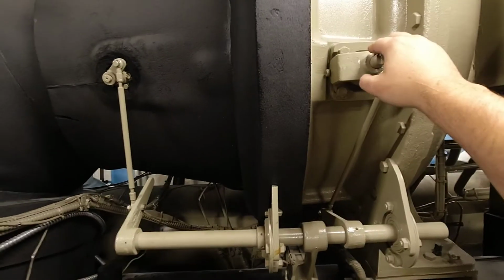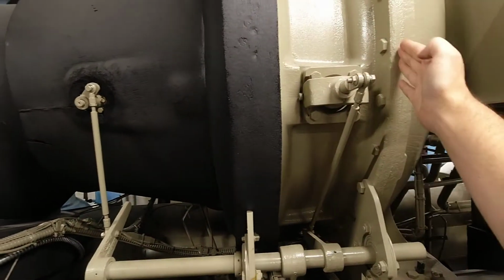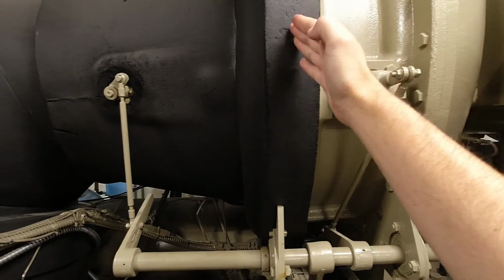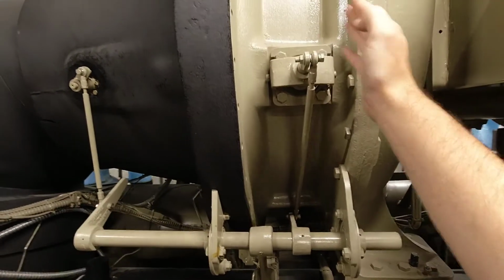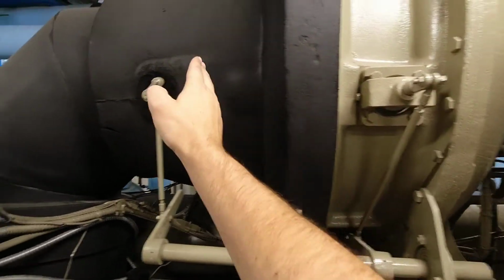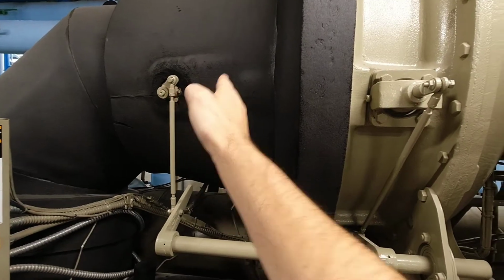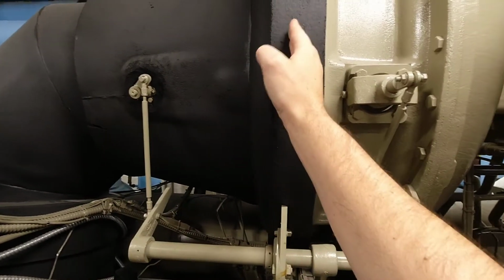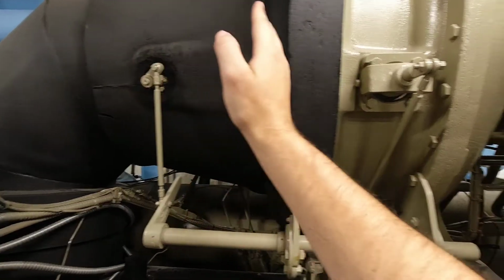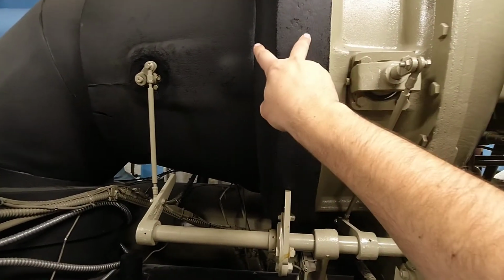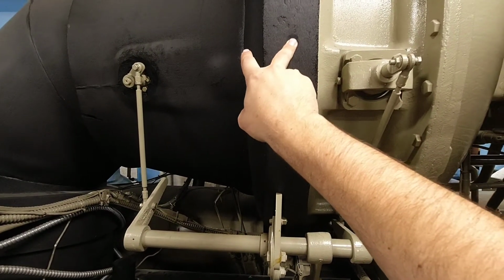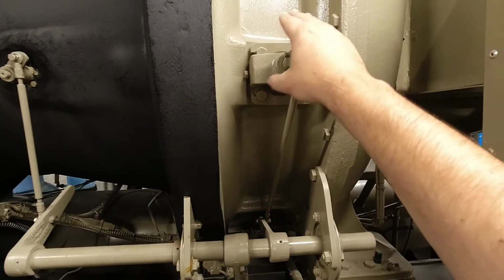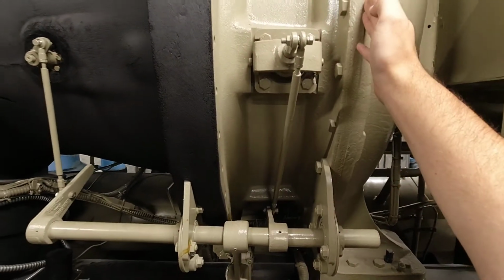Now, if this was a CVHE, this is your 1st stage, your 2nd stage. Impellers right here at these joints. If this was a CVHE, you would have a 3rd joint right here that would not be insulated. This insulated joint would be a little further over, and between the 1st and 2nd stage there would not be a guide vane. This guide vane would still be on the 3rd and final stage impeller.